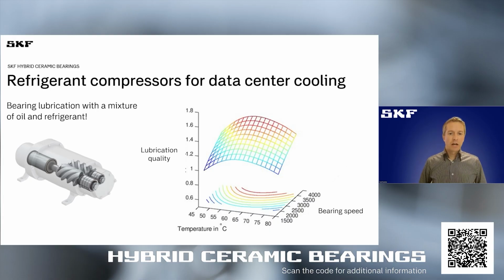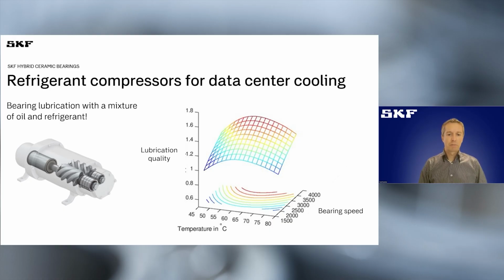The lubrication of the bearings in these screw compressors is really key for the success of this machine. As you can see in the diagram on the right-hand side, it gives you an illustration of how this lubrication quality varies in different areas of the operating map based on speed and temperature, but also depending on the use of the refrigerant and the oil and how the oil is diluted by this refrigerant.